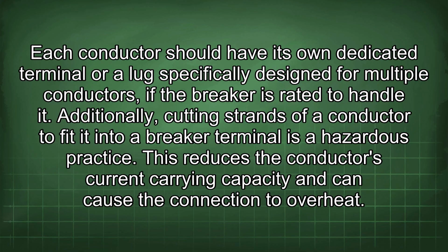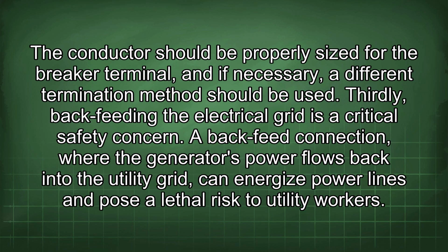rated to handle it. Additionally, cutting strands of a conductor to fit it into a breaker terminal is a hazardous practice. This reduces the conductor's current carrying capacity and can cause the connection to overheat. The conductor should be properly sized for the breaker terminal, and if necessary, a different termination method should be used.